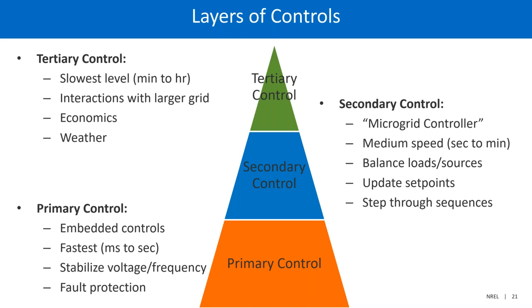There are different layers of controls typically seen on a microgrid, broken into three main categories. The top level is the tertiary control, very slow, typically minutes or hours. It handles all the interactions with the larger grid, dealing with economics or weather. So very slow moving actions are determined by the tertiary controller.